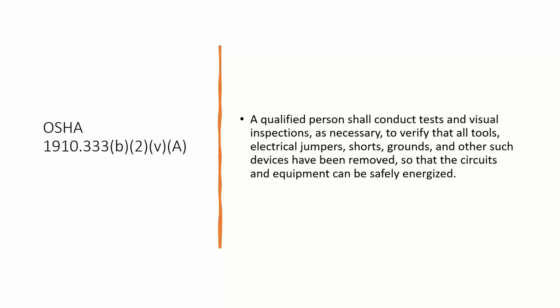Mm-hmm. So that's an example of leaving a tool or jumpers or grounds on. But you've got to be so careful that you haven't left a little piece of wire, especially if you're doing a lot of testing and you have to make little jumpers out of number 12 wire on your breaker to do some megger testing or high pot testing, and you leave a piece lying inside the breaker. You're going to have problems, big problems.